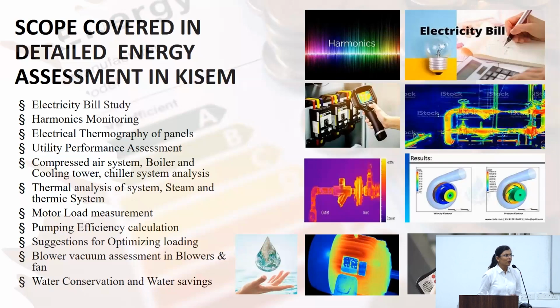Next thing is boilers and cooling towers. In the boiler also, sometimes, if we are talking about small things, the insulation is damaged. So if we remove the insulation, or do proper insulation, the losses should be minimized. We also study the steam consumption and all. And apart from that, we are also monitoring the flue gas parameters. Like in flue gas parameters, if the excess air is more, how to control it so that our fuel consumption will reduce.